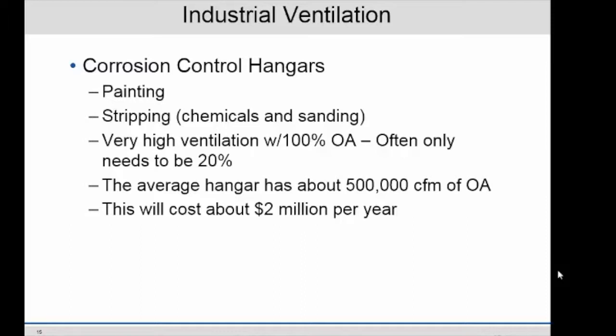You have to have humidification for when they're painting, yes. They've got to maintain about 40% relative humidity. So that's another problem, because they never last. These steam humidification systems don't last. So we prefer going to other types of systems that are not just steam injected into the ductwork. Go with something like a Nortec system that's gas-fired. Excuse me?